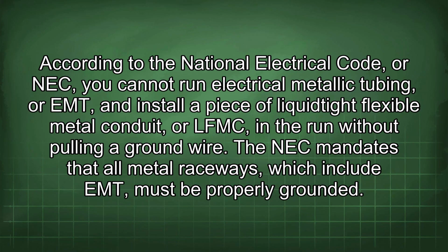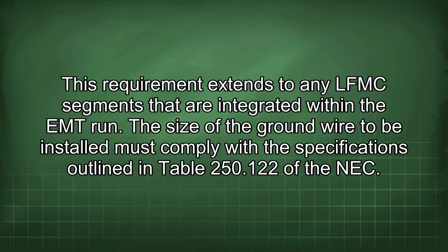According to the National Electrical Code, or NEC, you cannot run electrical metallic tubing, or EMT, and install a piece of liquid-tight flexible metal conduit, or LFMC, in the run without pulling a ground wire. The NEC mandates that all metal raceways, which include EMT, must be properly grounded. This requirement extends to any LFMC segments that are integrated within the EMT run.